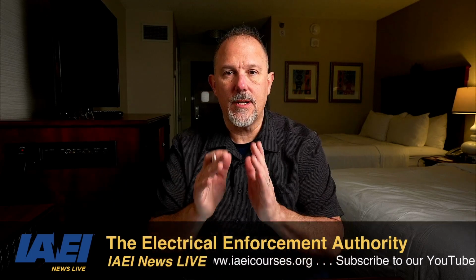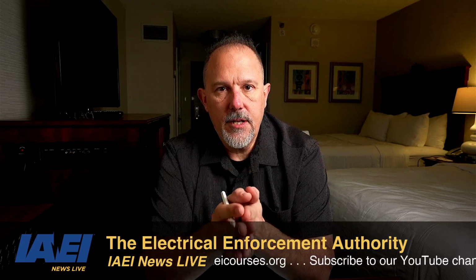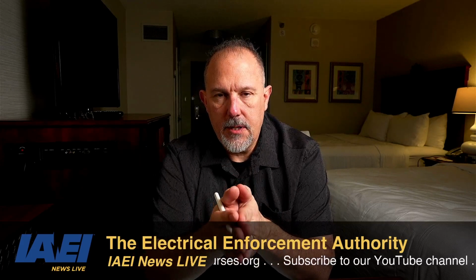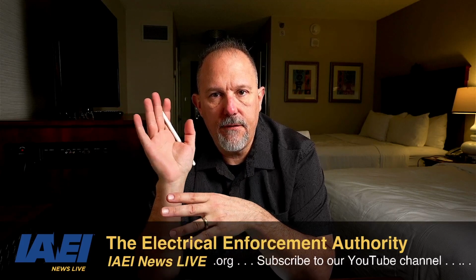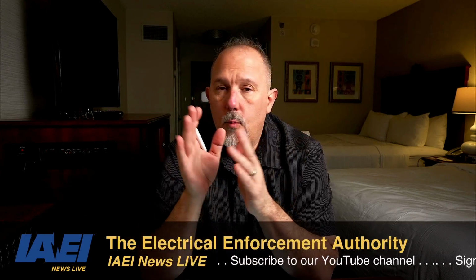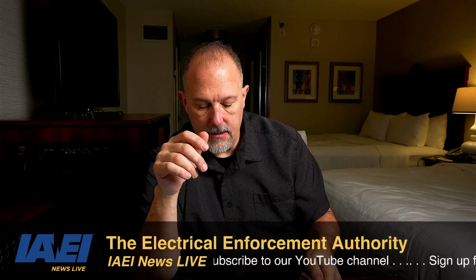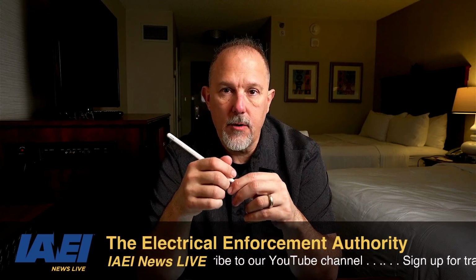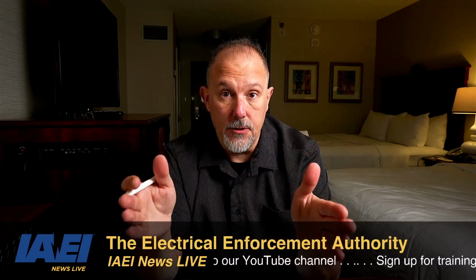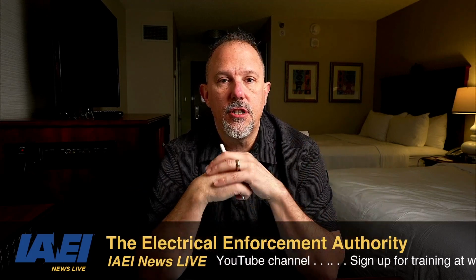So we talked a little bit about separately derived versus non-separately derived. We know that the conductors from the generator, whether or not they're protected, whether you have an overcurrent device in the generator or not, I don't really care. They're feeders because they meet the definition of feeders.